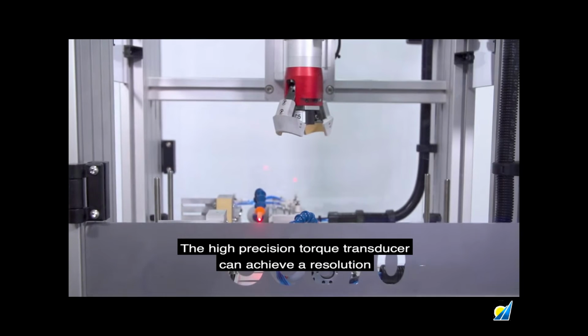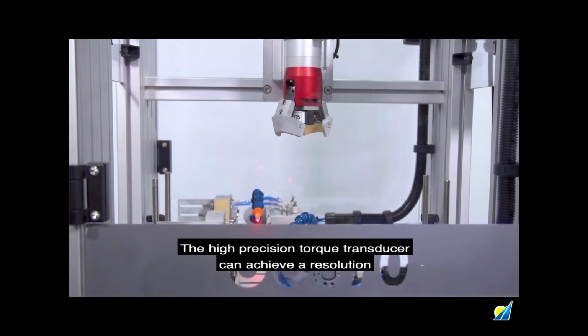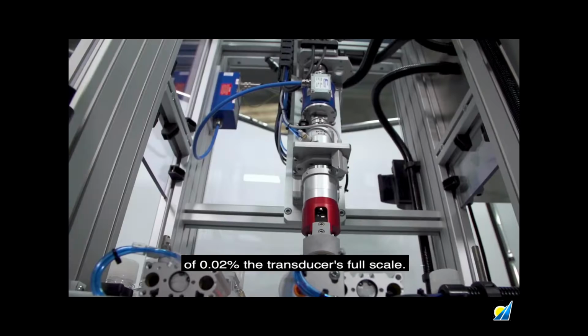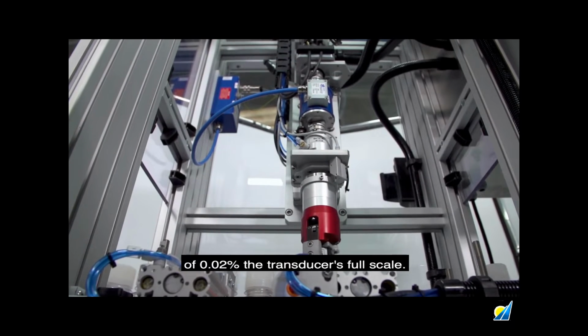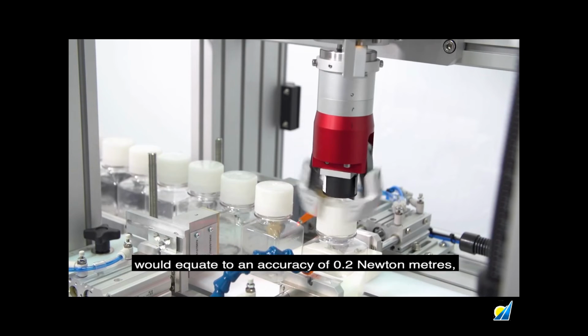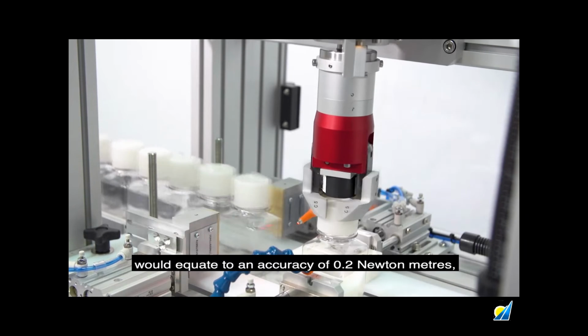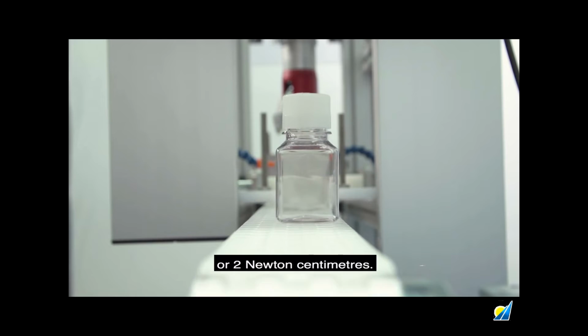The high-precision torque transducer can achieve a resolution of 0.02% of the transducer's full scale, which in this demonstration's case would equate to an accuracy of 0.2 Newton meters, or 2 Newton centimeters.